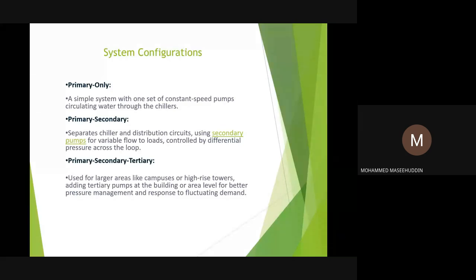Then there is a second circuit, which is the primary-secondary circuit, called the secondary chilled water circuit, which has the pumps near the chillers to supply the chilled water which has already been chilled, the delta T is achieved, at about 7 to 8 degrees centigrade off coil. This water is sent to the building loads in various equipment like air handling units and fan coil units, and it reaches up to the last fan coil unit, which is the longest route in the building, and then again comes back to the water source. From there, the primary chilled water pump will again pump it back to the chiller. So that's why it's a closed circuit.